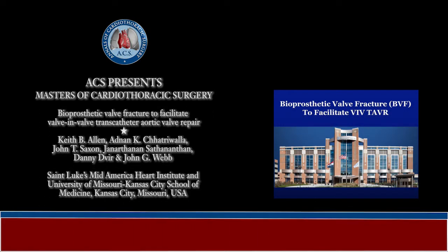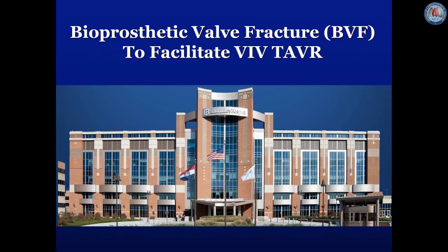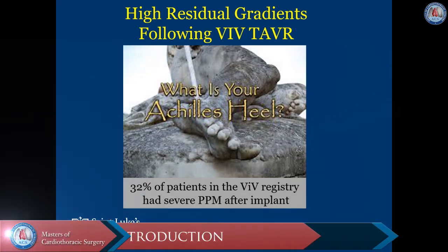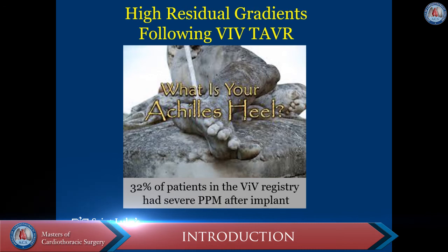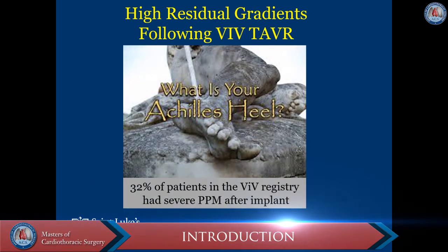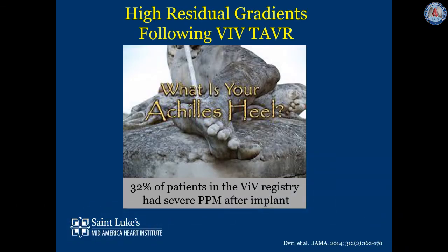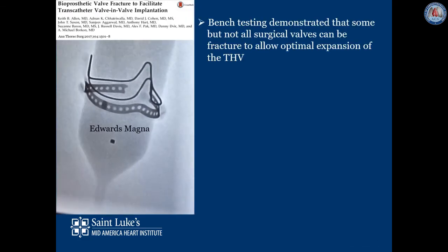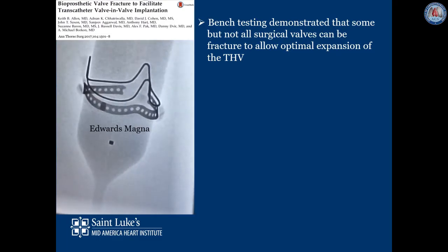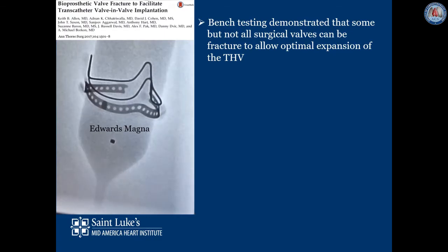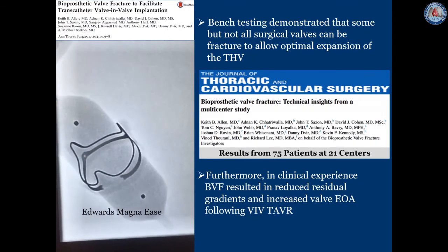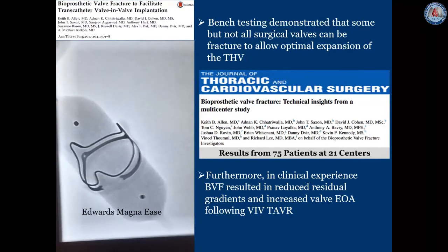In this video, we'll provide background and clinical data on bioprosthetic valve fracture, or BVF, as well as present several case vignettes. High residual gradients following valve-in-valve TAVR remain an Achilles heel for this procedure, with 32% of patients in the valve-in-valve registry reporting severe PPM after implantation. Bench testing demonstrated that some, but not all, surgical valves could be fractured to allow optimal expansion of the transcatheter heart valve. In recent clinical experience, BVF resulted in reduced residual gradients and increased valve EOA following valve-in-valve TAVR.